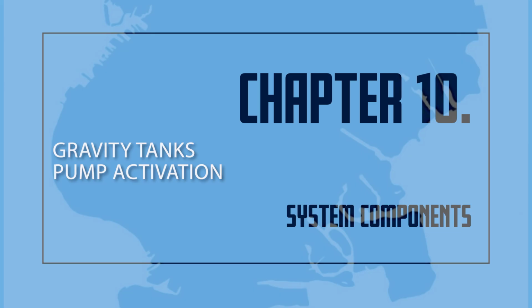When manually activated pumps are installed, they are usually used in combination with a gravity tank or a pressure tank. These tanks are designed to operate when there is a pressure drop in the fire protection system. The operation of the pressure tank and the triggering of its supervisory devices, or alarms, alert the certificate of fitness holder that the fire pump must be activated. The certificate of fitness holder, or another responsible individual, should then manually activate the fire pump according to the manufacturer instructions. Manually operated fire pumps are often found in industrial and manufacturing occupancies having personnel on the premises at all times. The certificate of fitness holder may only activate a manually operated vertical fire pump arranged as described above. Sometimes remote push buttons are used to activate the pump. These remote push buttons are designed to start the pump but not to stop the fire pump.